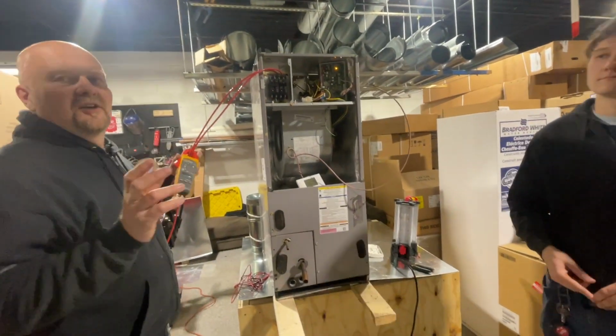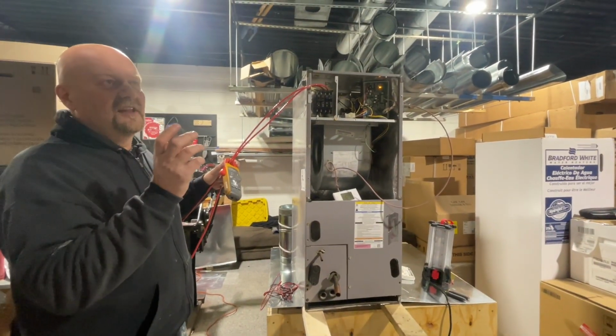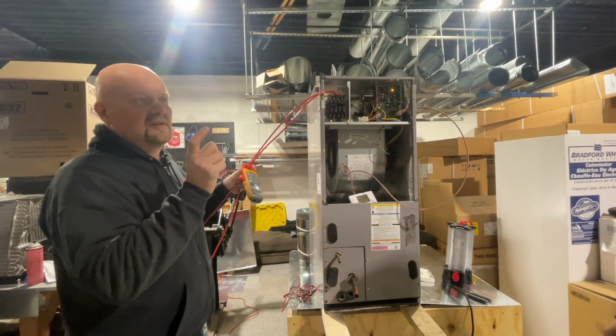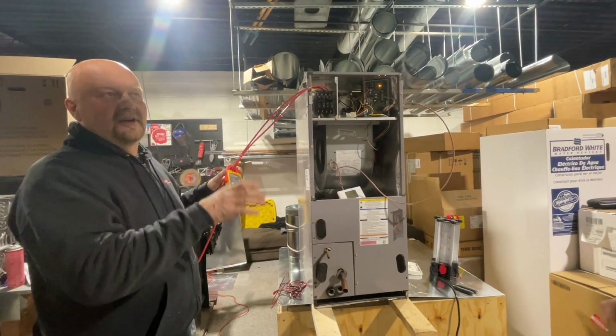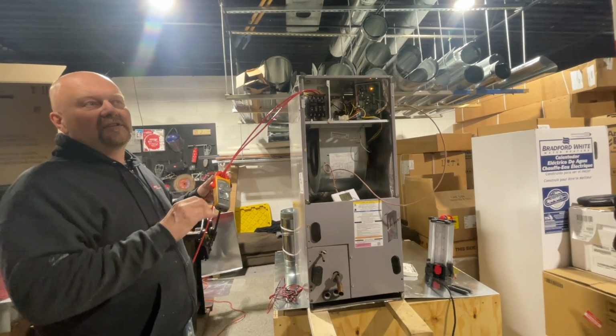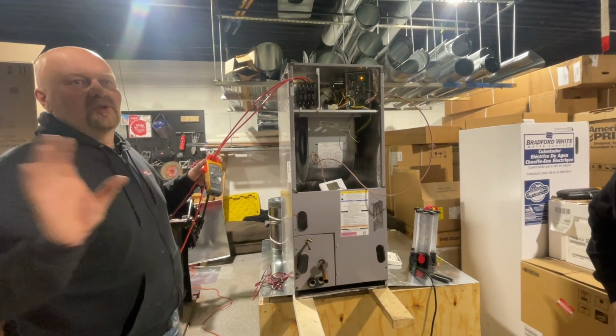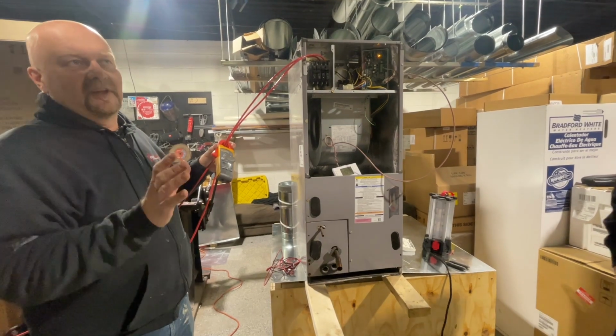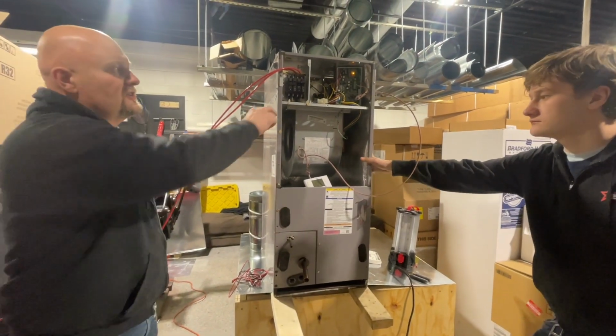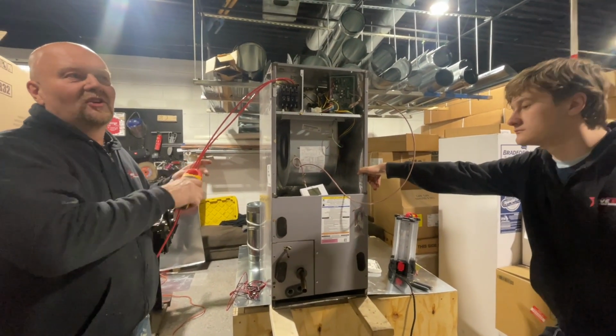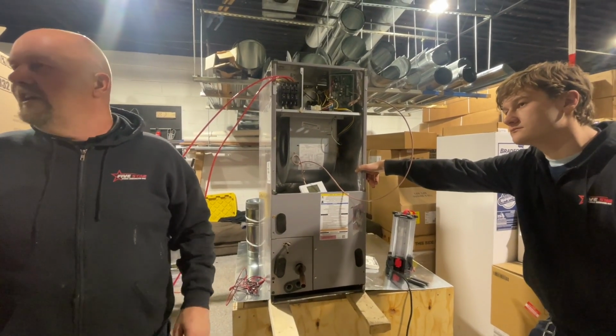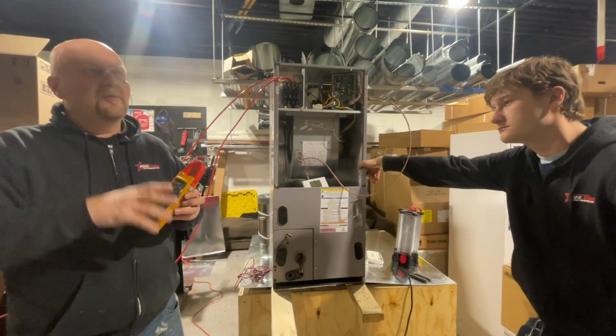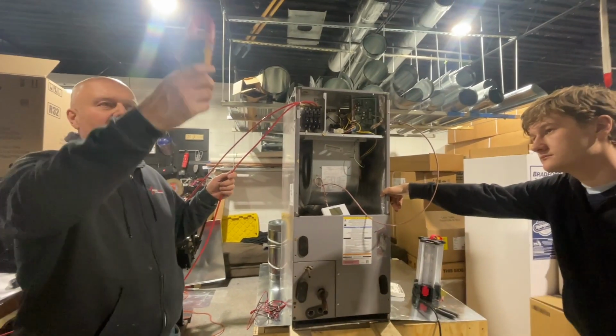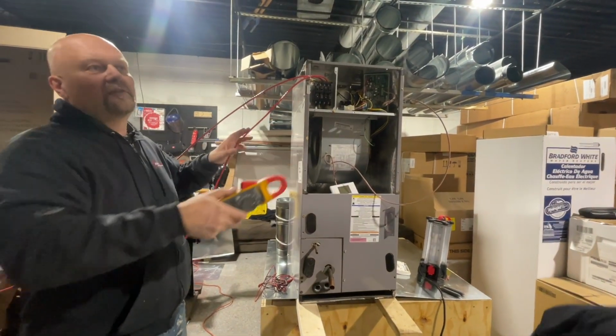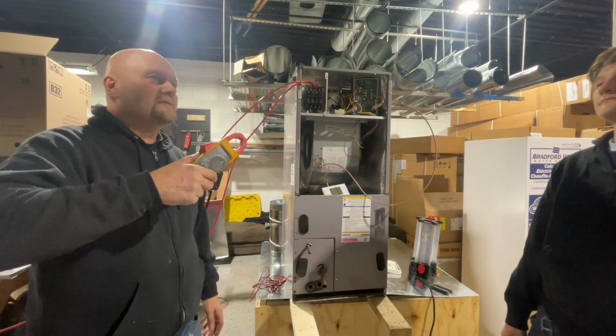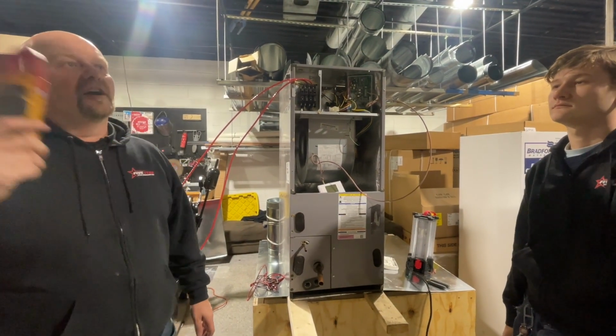Because there'll be too much. See, part of our classes I really want to focus on is specific information, like 5 or 10 points at best. Because I think in the past, when we did classes with Derek, there was too much information and nobody remembered anything. That's what I noticed. So I want to do this where we spend no more than 30, 45 minutes and actually remember something. So if all you guys remember from this is you need an amp meter, you check amps times volts are watts, and kilowatts times 3,500 are BTUs.